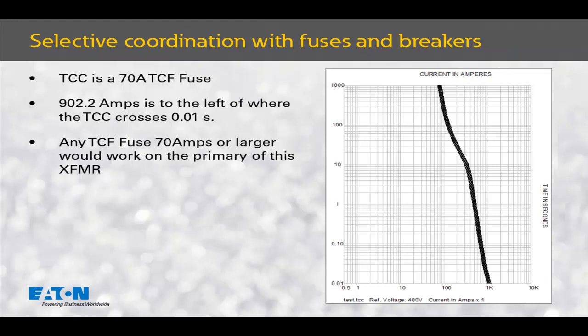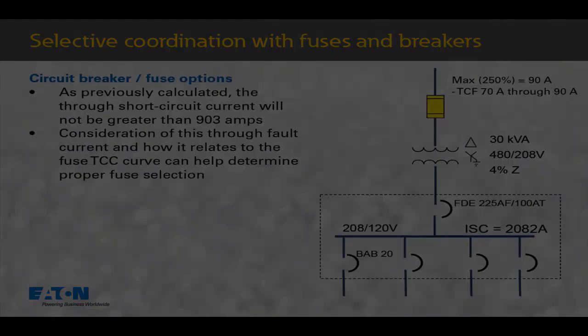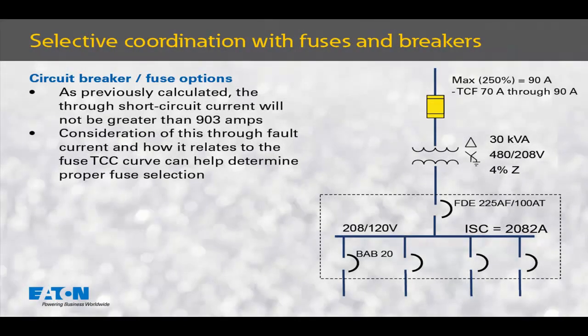Regardless of the circuit breaker solution that selectively coordinates on the secondary, the TCF 90 can be selected as this is the maximum size overcurrent protective device permitted by the National Electrical Code. The fuse solution on the primary of this transformer does provide some flexibility in moving to a smaller fuse for tighter protection below the maximum permitted by the NEC, should the engineers decide to do so. The only restriction outside of the maximum fuse size permitted by the NEC is the inrush current of the transformer.